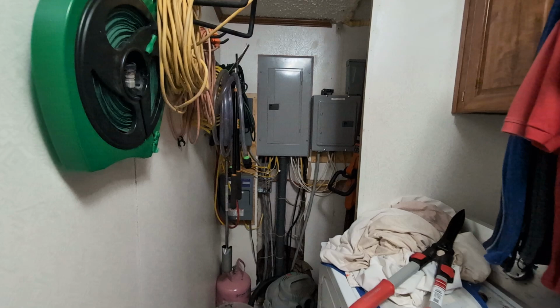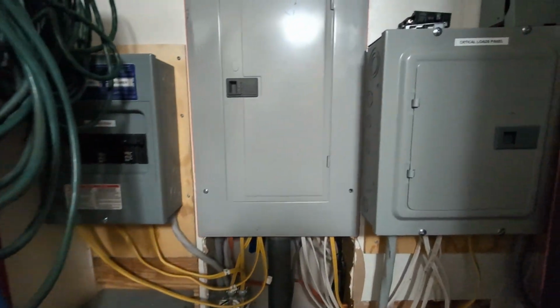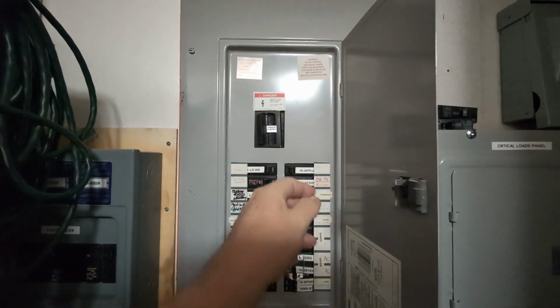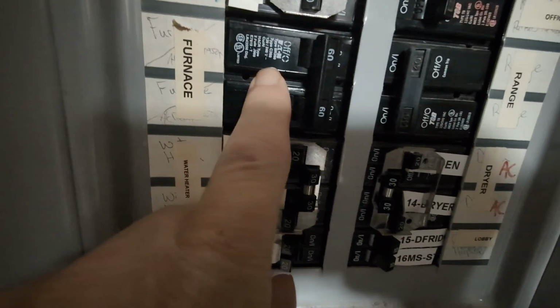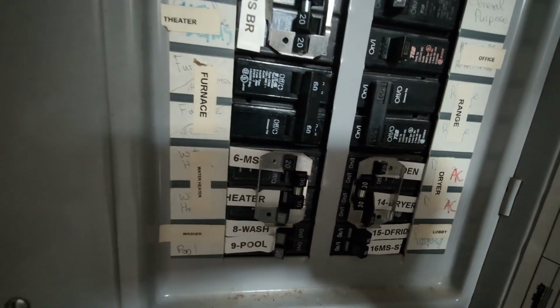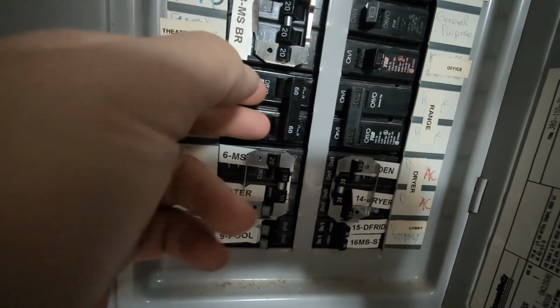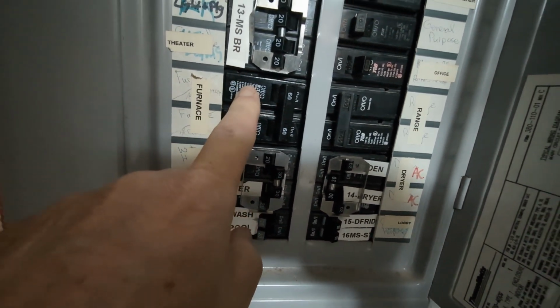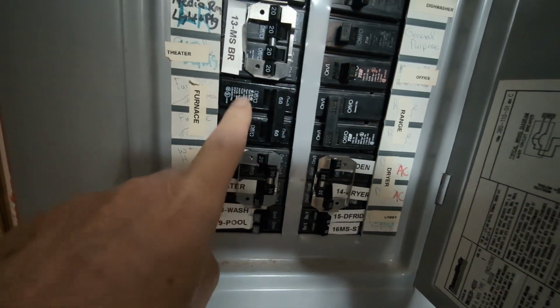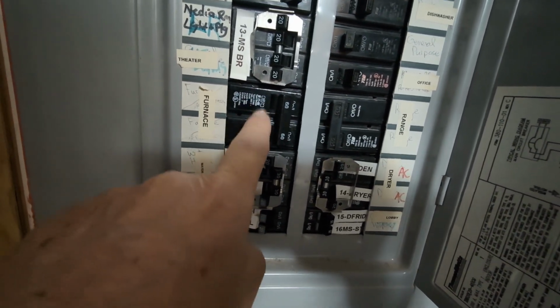So just like the 48 volt system, the 24 volt system, everything originates here at the main panel. So I have 200 amp service coming in, and then what I've done is this circuit here marked furnace is actually the pass-through, the live feed, or the grid feed to my 48 volt inverters and to my 24 volt inverters. So this is how they get power. Power comes out of that 60 amp breaker into this large service entrance cable. Now this service entrance cable is capable of handling 100 amps at 240 volts. And it also has a ground wire in it.